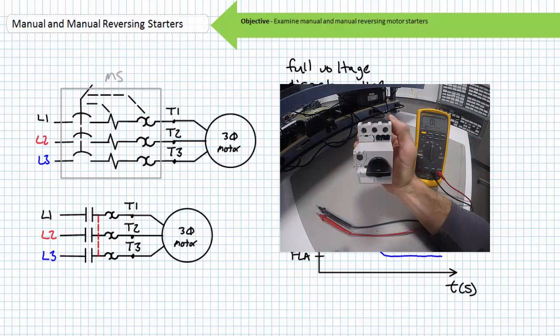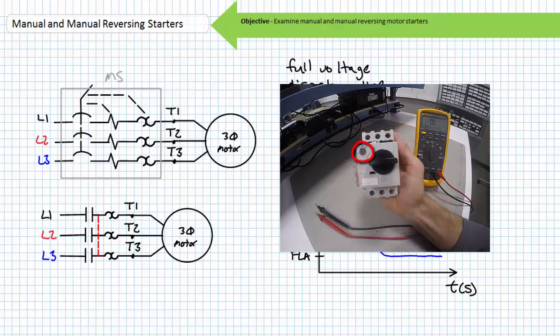Manual motor starters often feature a lockout and tagout mechanism on the front dial. An operator wishing to service the motor can open the contacts, pull out a locking slider and insert their individual lock and tag. Additionally, motor starters often feature an adjustable current setting for the overload. This allows a motor starter to be employed for a range of applications.